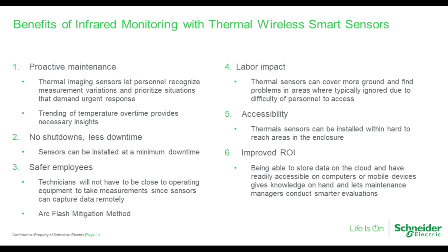Also, there would be a labor impact. You don't need somebody going around doing thermographic imaging anymore because the thermal sensors are online all the time. So due to that, and difficulty of access into some of the equipment, you no longer have to have somebody going around opening doors, looking into things, and again, being in an unsafe situation.